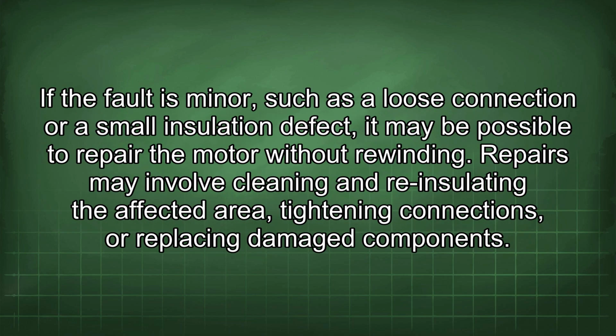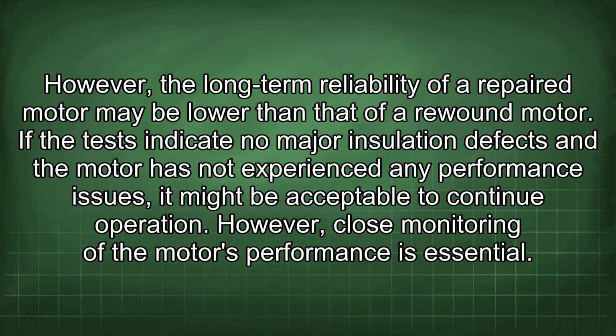If the fault is minor, such as a loose connection or a small insulation defect, it may be possible to repair the motor without rewinding. Repairs may involve cleaning and re-insulating the affected area, tightening connections, or replacing damaged components. However, the long-term reliability of a repaired motor may be lower than that of a rewound motor.